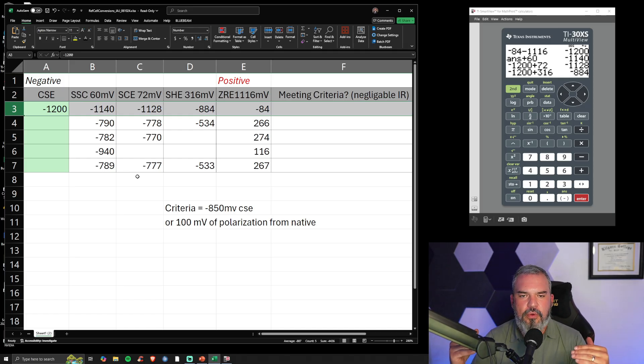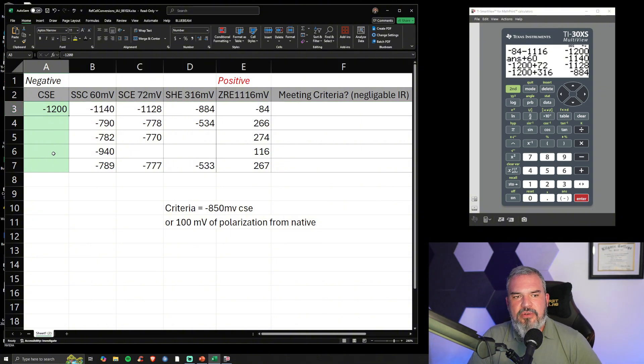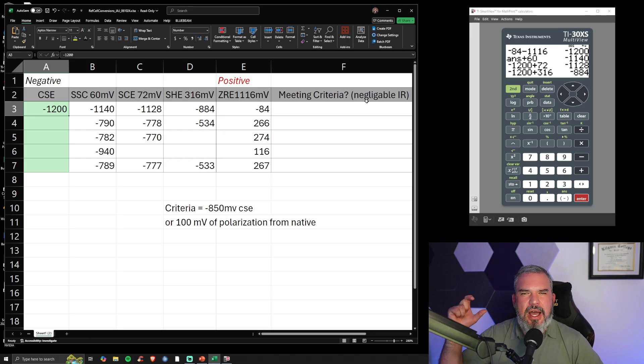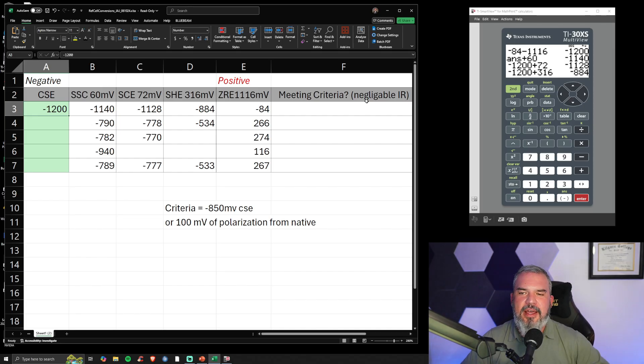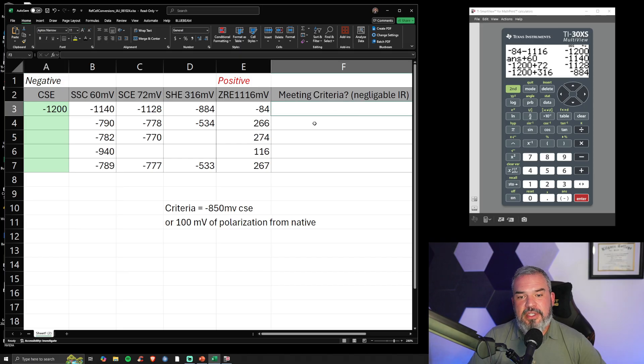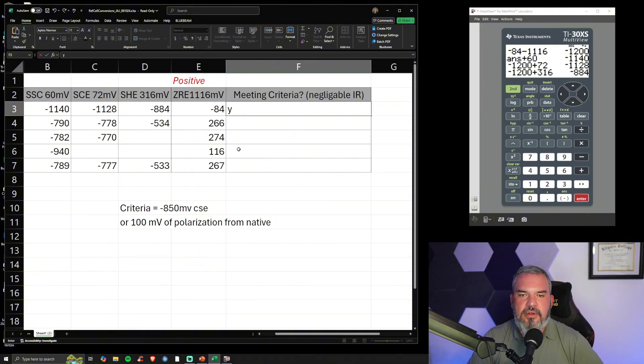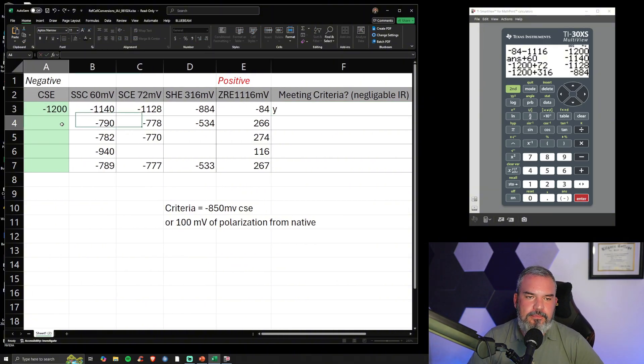Concentrating on Row 3: if our criteria for effective cathodic protection is −850 millivolts with respect to a copper-copper sulfate reference electrode, and we assume negligible IR error, did we meet criteria? With a CSE reading of −1,200 millivolts, yes — we definitely meet the −850 mV criterion. The answer is yes.